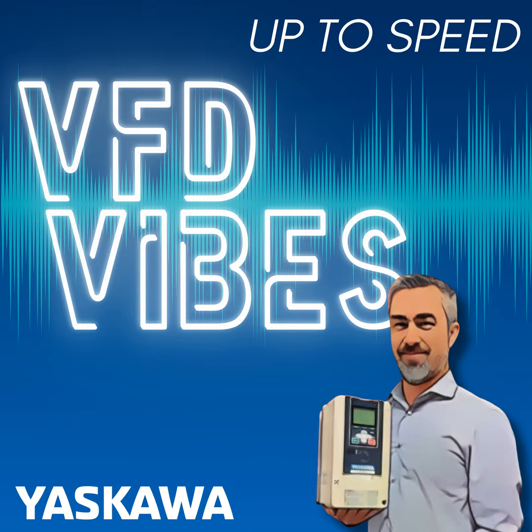If you were to run into probably 99% of the factories, large buildings, any facility that's got 480 volts, three-phase, it is most likely connected as a Y, 277 line-to-neutral voltage with that neutral solidly grounded at the service entrance of the building.